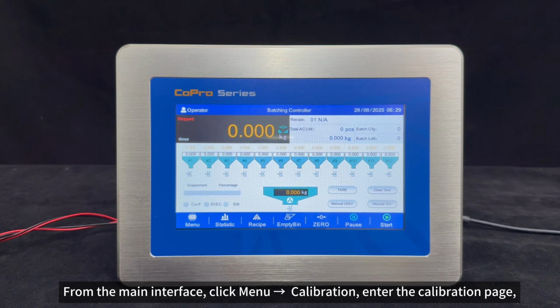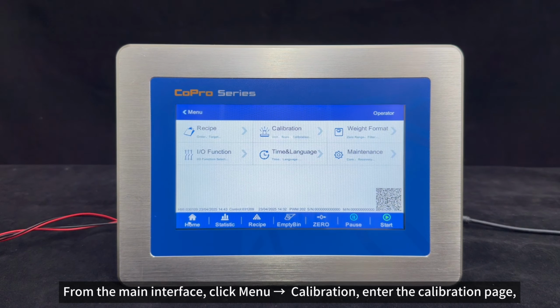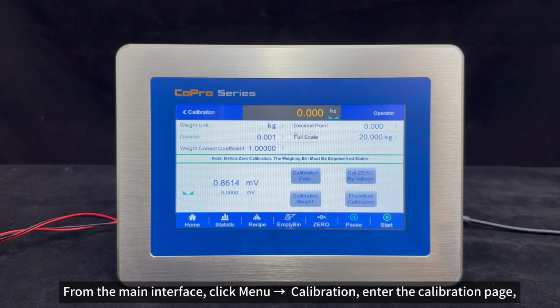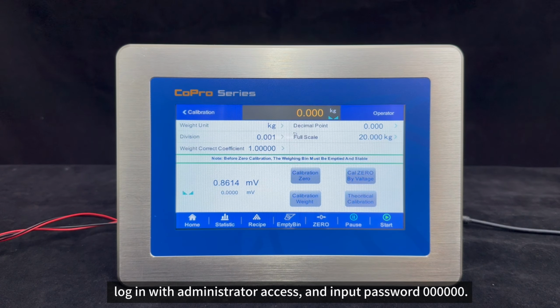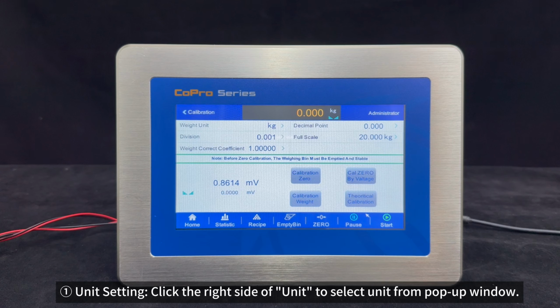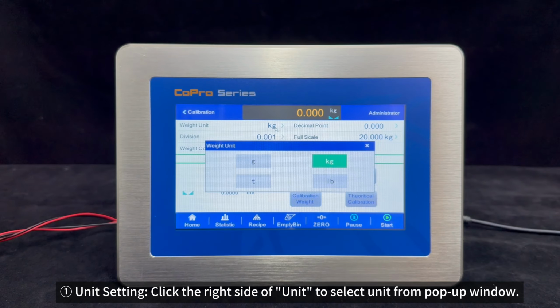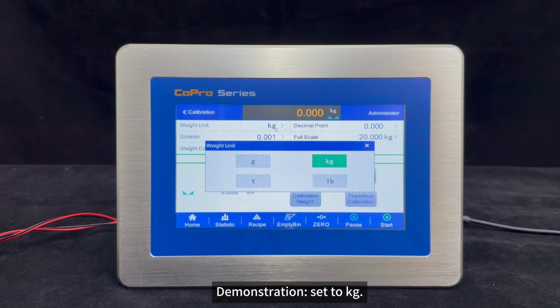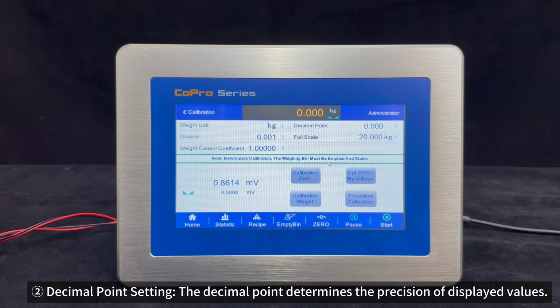From the main interface, click Menu, Calibration, enter the calibration page. Log in with administrator access and input password 000000. Unit setting, click the right side of unit to select unit from pop-up window. Demonstration, set to kilogram. Decimal point setting, the decimal point determines the precision of displayed values.